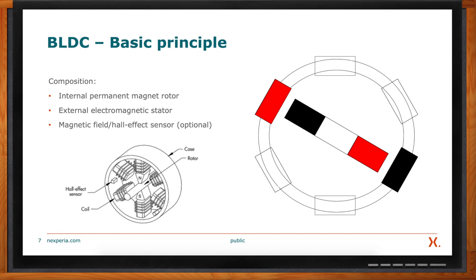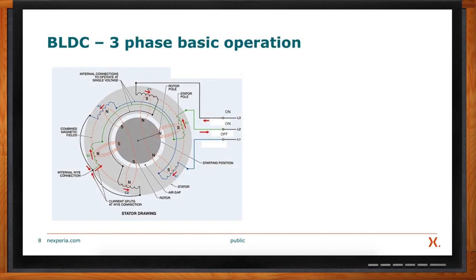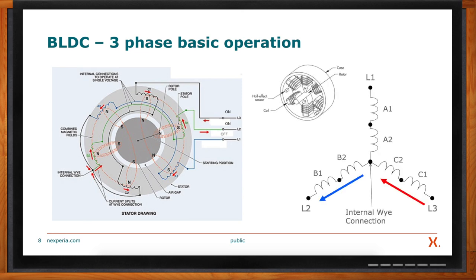So that's the mechanics of the motor — what about the electrical piece? We have to get into the electronic part now. Here's a diagram of what the coils look like around the outside of that permanent magnet that spins inside. For all these coils, you've only got three wires going into this motor, called L1, L2, and L3. This is what's called an internal Y connection — it's the most common. By determining what voltage you put on the combination of L1, L2, or L3, you determine the polarity of the magnets on the outside of the coil. By alternating the electricity through L1, L2, and L3, you can move the electromagnetic field around the outside of the motor, and the permanent magnet inside follows. Three wires, and you have all this control.